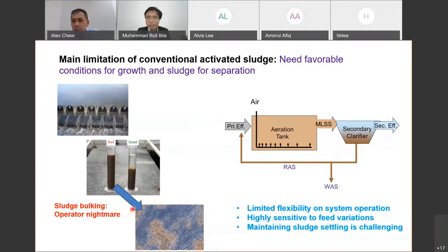What is sludge bulking? Normally in this clarifier, we want to easily separate the treated water and the sludge. But when your sludge is bulking, this process doesn't work. And this is how it looks: instead of producing clear effluent, you produce muddy-like effluent. One of the reasons this happens is the overgrowth of what we call filamentous bacteria.